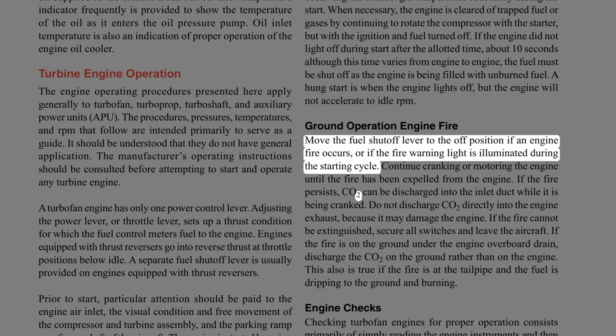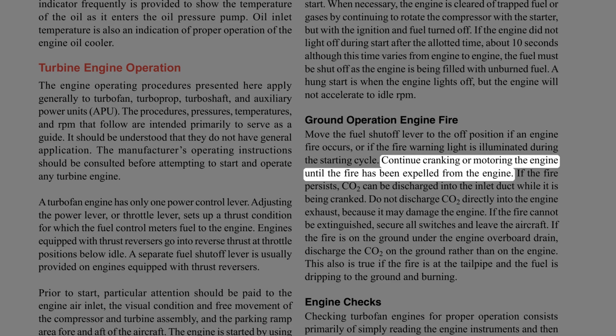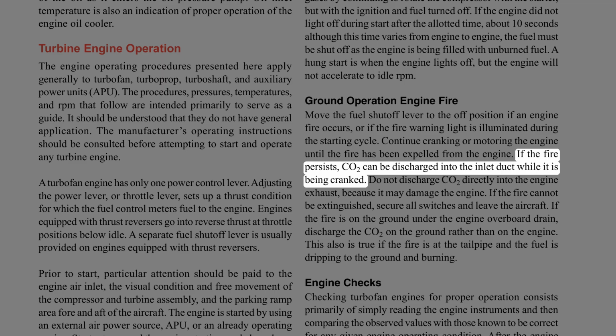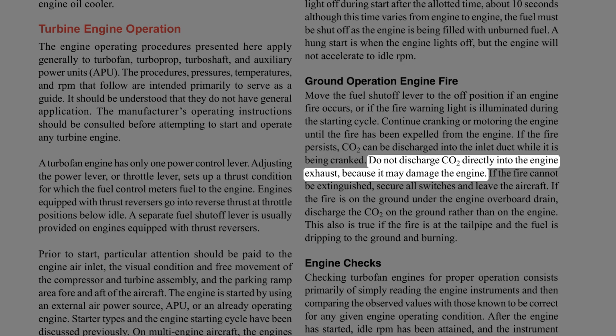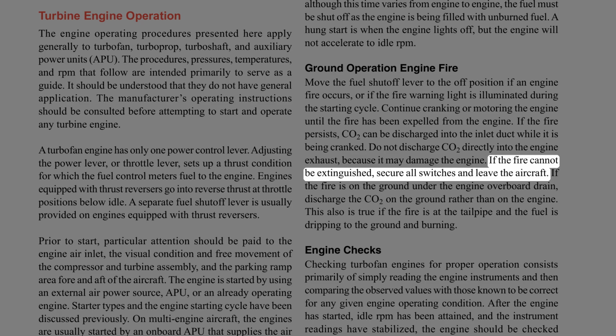Move the fuel shutoff lever to the off position if an engine fire occurs, or if the fire warning light is illuminated during the starting cycle. Continue cranking or motoring the engine until the fire has been expelled from the engine. If the fire persists, CO2 can be discharged into the inlet duct while it is being cranked. Do not discharge CO2 directly into the engine exhaust, because it may damage the engine. If the fire cannot be extinguished, secure all switches and leave the aircraft.